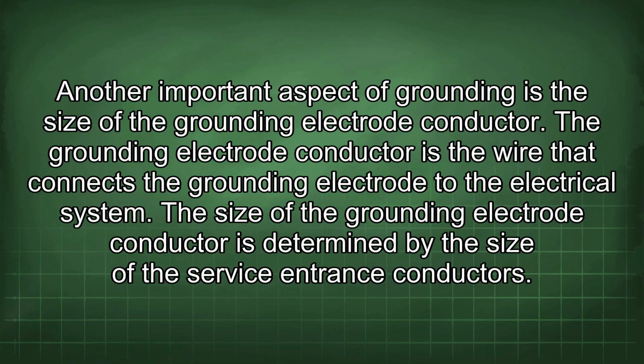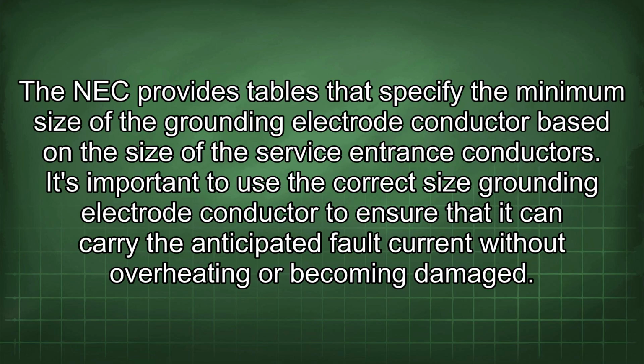Another important aspect of grounding is the size of the grounding electrode conductor. The grounding electrode conductor is the wire that connects the grounding electrode to the electrical system. The size of the grounding electrode conductor is determined by the size of the service entrance conductors. The NEC provides tables that specify the minimum size of the grounding electrode conductor based on the size of the service entrance conductors. It's important to use the correct size grounding electrode conductor to ensure that it can carry the anticipated fault current without overheating or becoming damaged.